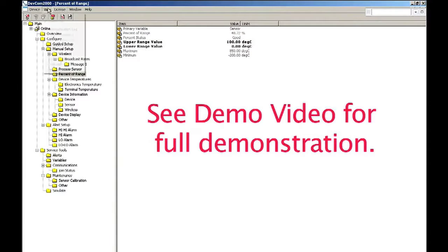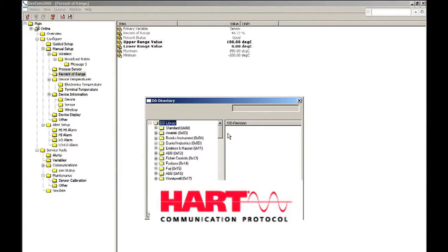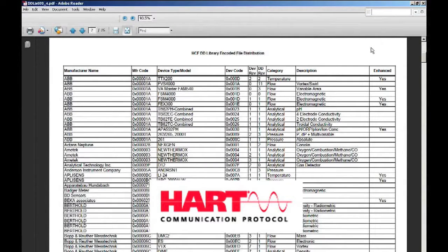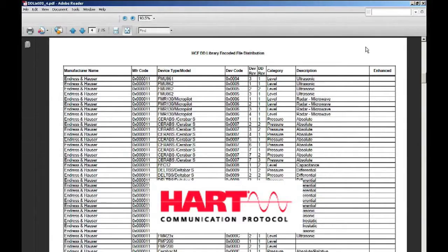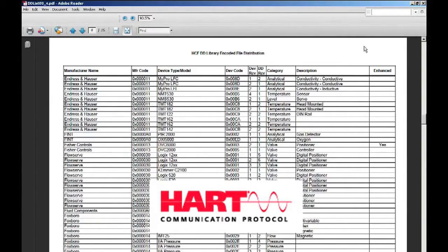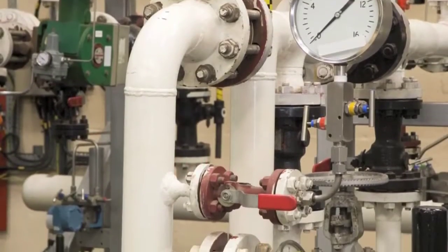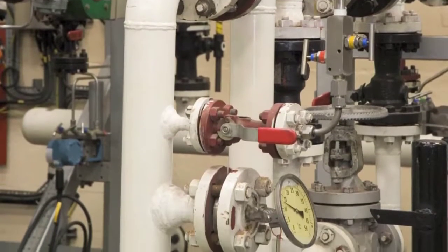Here you see a list of DDs in the DevCom 2000 software. DevCom 2000 uses the compiled device description binary file, the DD, developed by the device manufacturer and registered with the HART Communication Foundation. Each DD has been tested by the device manufacturer. This is an important point because, as a result, we know that every DD will work with the device, be it a transmitter or control valve.